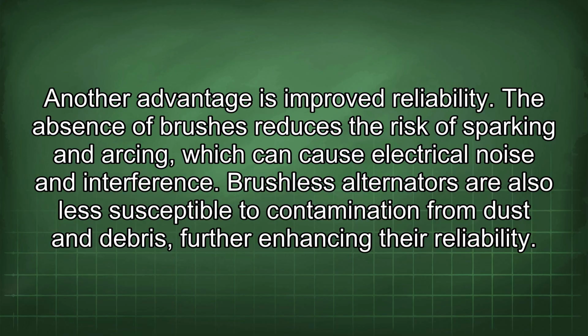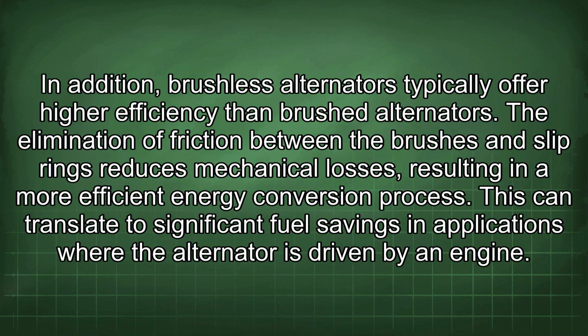The absence of brushes reduces the risk of sparking and arcing, which can cause electrical noise and interference. Brushless alternators are also less susceptible to contamination from dust and debris, further enhancing their reliability. In addition, brushless alternators typically offer higher efficiency than brushed alternators. The elimination of friction between the brushes and slip rings reduces mechanical losses, resulting in a more efficient energy conversion process. This can translate to significant fuel savings in applications where the alternator is driven by an engine.